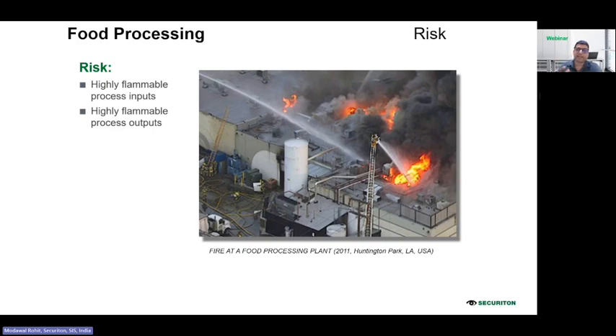For the manufacturing area, you have highly flammable process inputs. Whenever you go into a manufacturing area, you find a lot of process inputs. For example, there are a lot of oils, sugar dust, flour dust, alcohol-based flavorings, and many kinds of packaging materials. The risk factor is the flour and the sugar present in the atmosphere. It creates a dust cloud, and eventually there might be a dust explosion. Then you have oil and solvents already present in the atmosphere, and they are prone to flash fires. Then packaging materials like plastic and cardboard, which ignite easily.